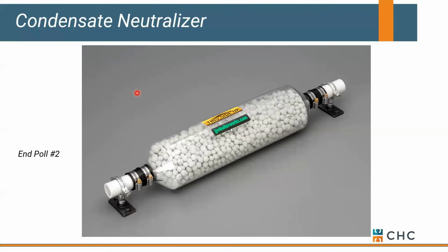Not all boilers are designed to handle it, okay? Condensation occurs due to low combustion air temperatures. A bit of a trick question. It's really based on low return water temperatures. So not so much on the air side, it's more based on the water side. Okay, that's going to affect our natural gas combustion process more than air temperatures. Typical pH range for condensate is 2 to 5 when measured at the boiler. That's a true statement. Condensate neutralizers are required for the boiler and the flue.